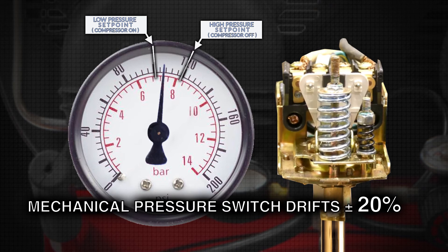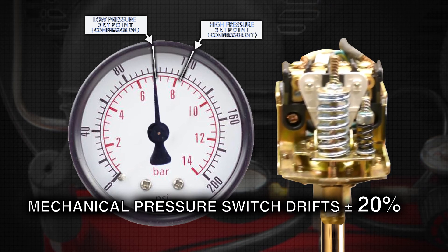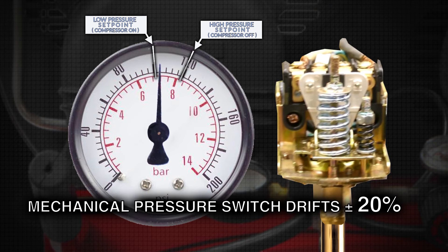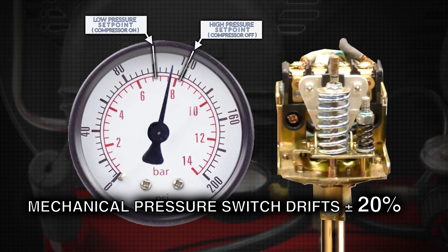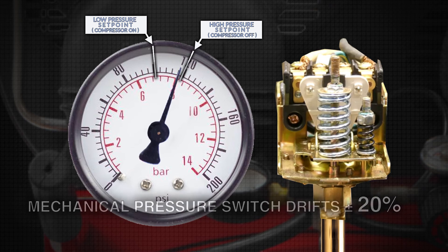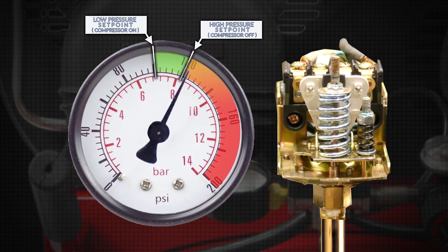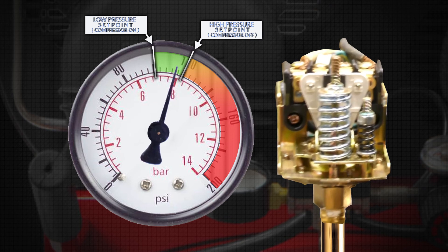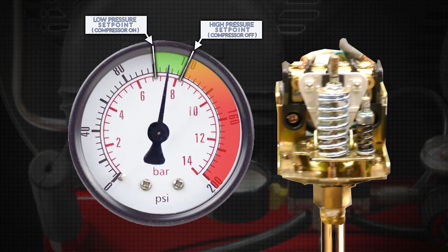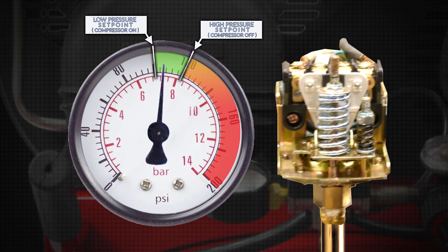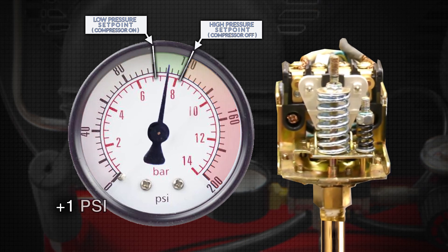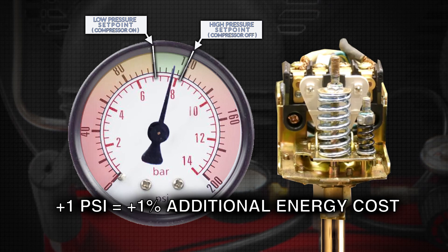If the pressure set points are not being checked and set daily, there can be a significant increase in energy consumption and operational cost. Unmonitored pressure can also be a safety concern. For each PSI above the set point, there is an increase in pump cycling time and power consumption in order to maintain the higher-than-necessary pressure setting. The overall energy cost to the owner is roughly increased 1% for each PSI above.